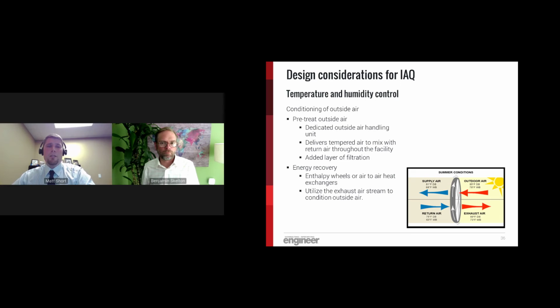Benny touched on energy efficiency earlier, and one common practice to help offset the energy required to treat the ventilation air is to provide energy recovery at this level. Often, this is a code requirement through the energy codes. This can be accomplished by using an energy recovery enthalpy wheel or air-to-air heat exchanger. These devices most often utilize exhaust air that's already conditioned to help alleviate the load from the outside air handler's cooling and heating coils, which ultimately alleviates central plant load.